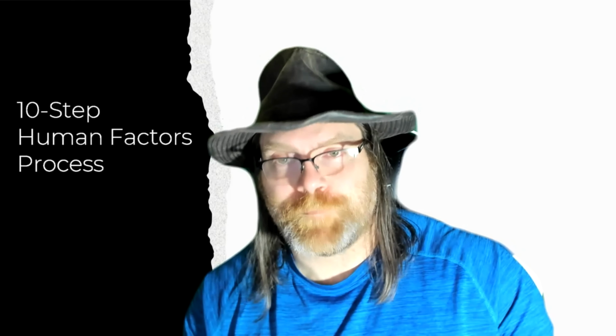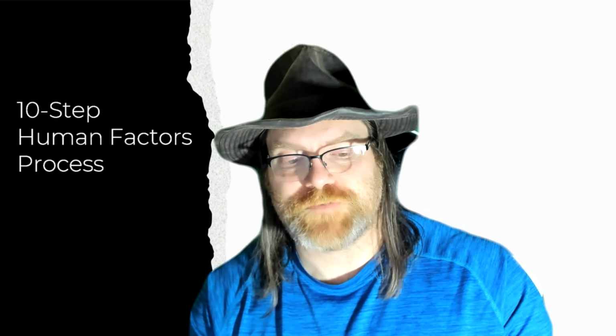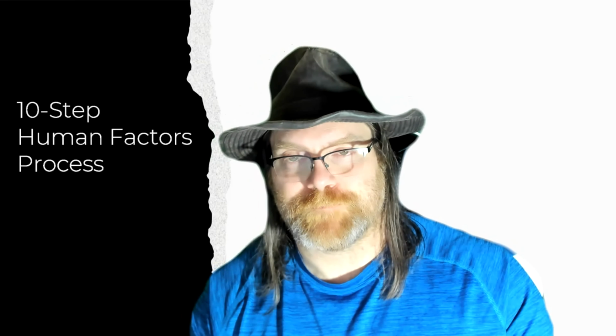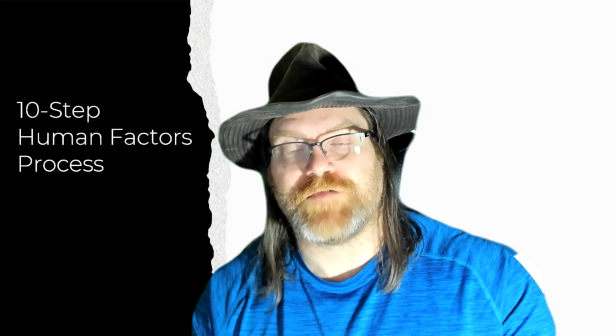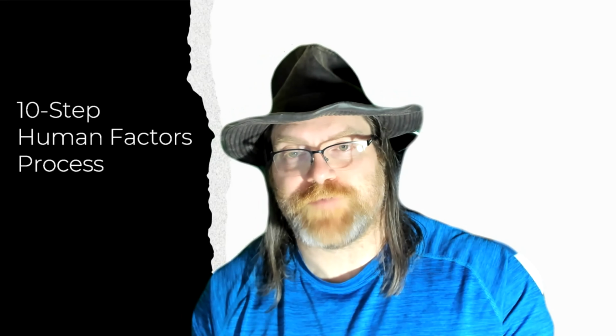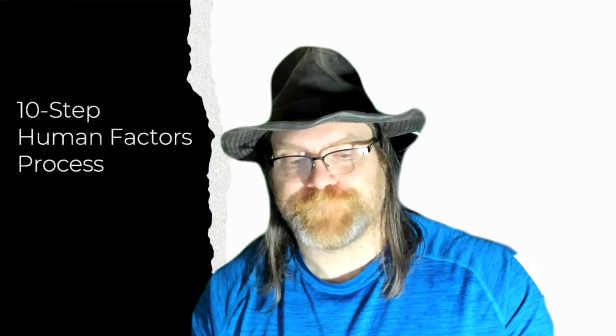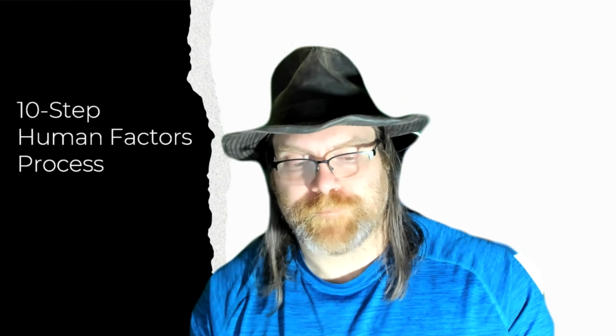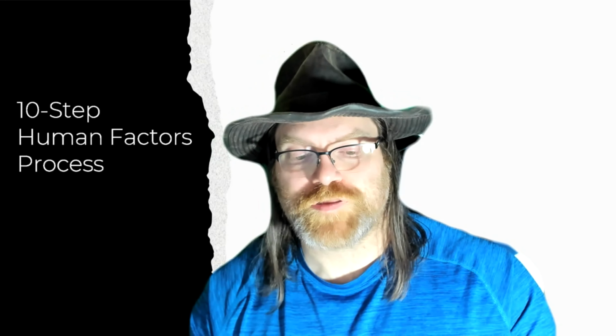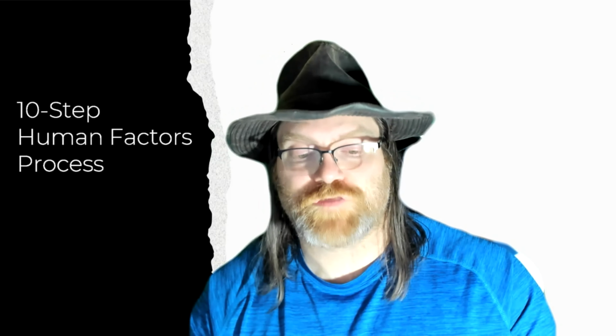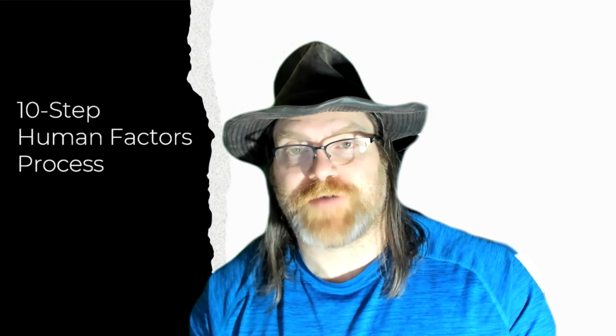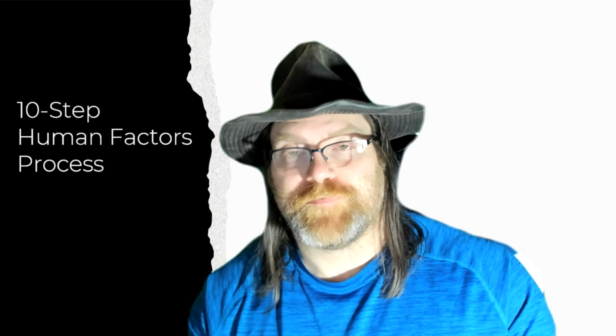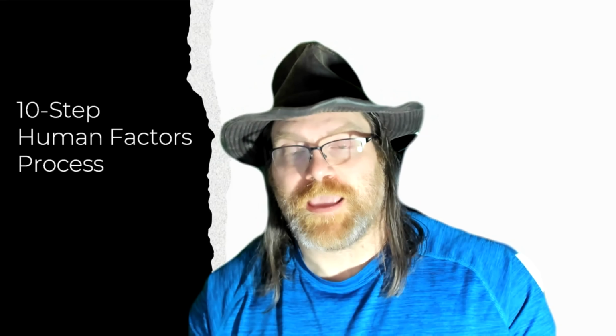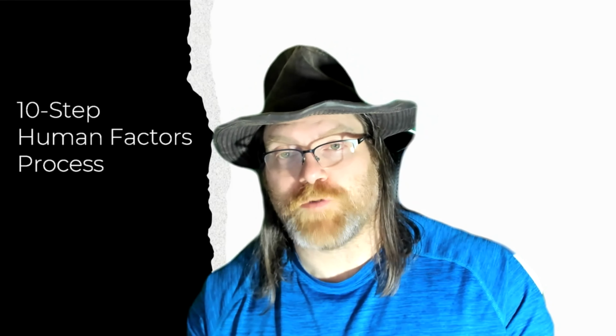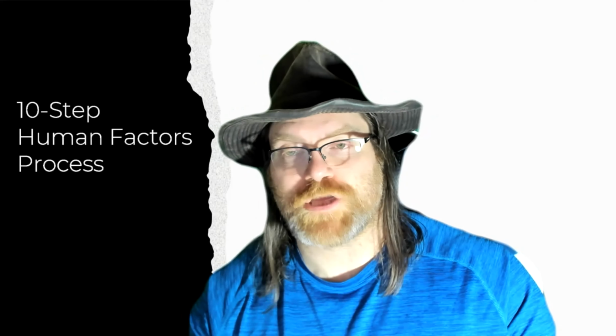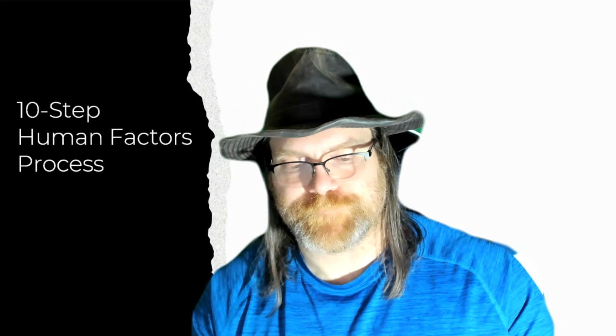Okay, the next step, now we're into the verification validation phase, summative testing. Summative testing is your final validation that your user interfaces work to prevent use errors. Number one, you need a prospective approved protocol. It's required. You need to identify what the IFU version is that's going to be used in this study. And if there are any changes between that and what you actually submit, you have to explain why those changes don't require you to repeat everything.